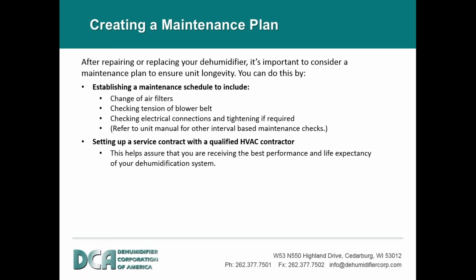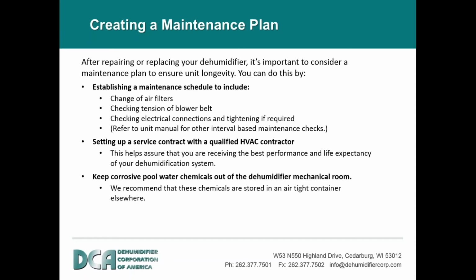Another consideration to keep in mind is the storage of corrosive pool water chemicals outside the dehumidifier mechanical room. Jim has touched base on that already, but they should be kept in a well-ventilated utility room, or sometimes they place them in a cabinet outdoors. One of the things to keeping your unit running also is to make sure that all the diffusers, return and supply, are unobstructed.